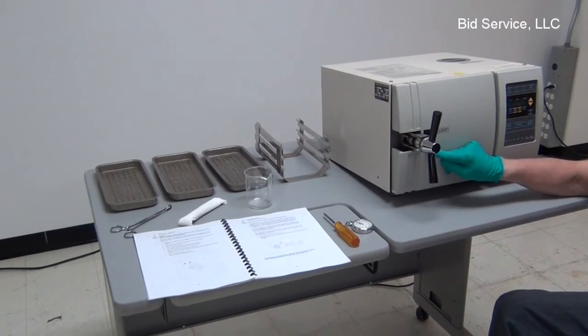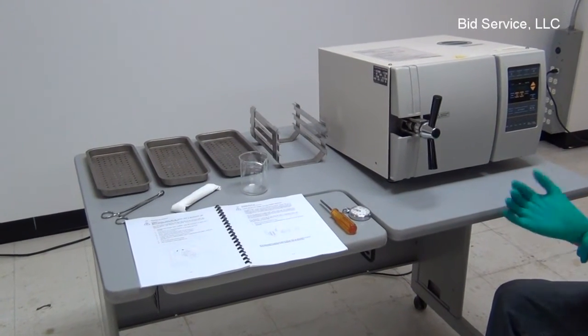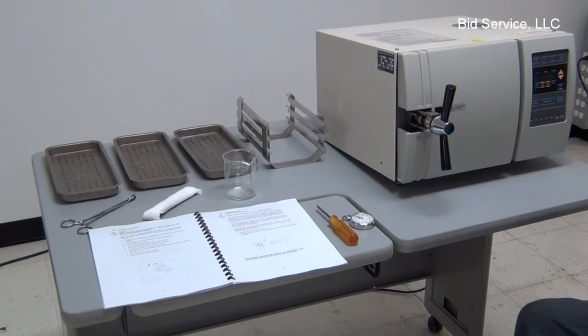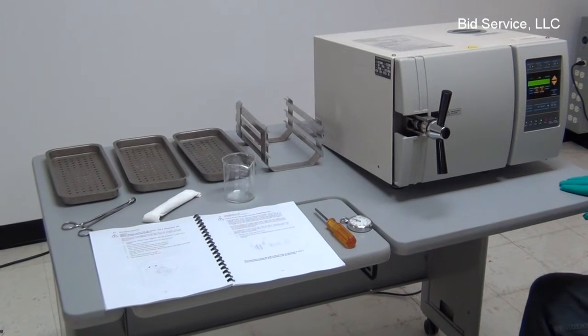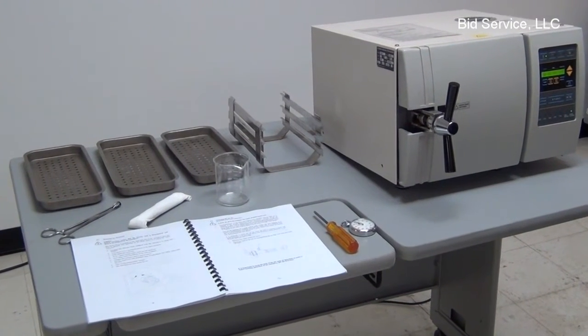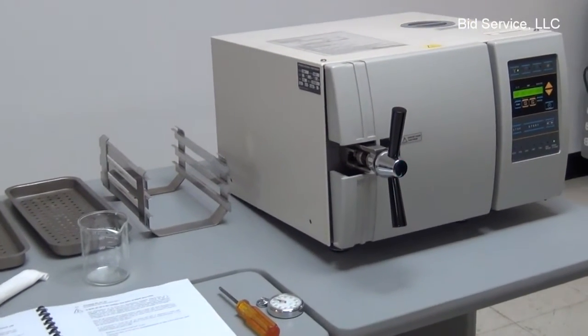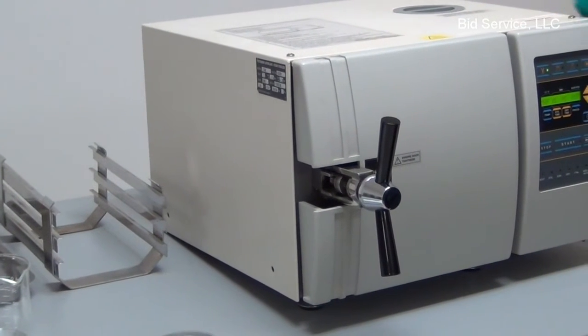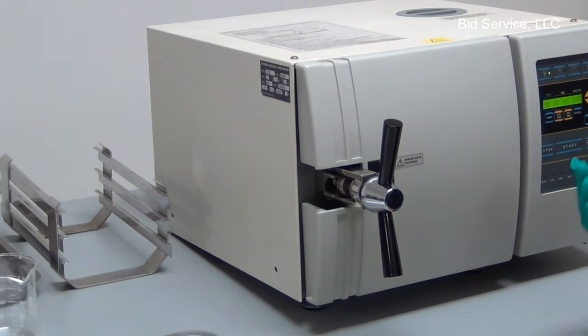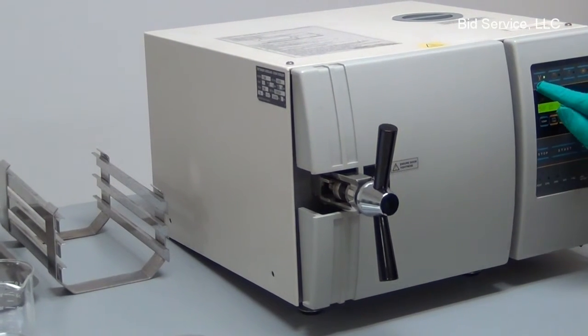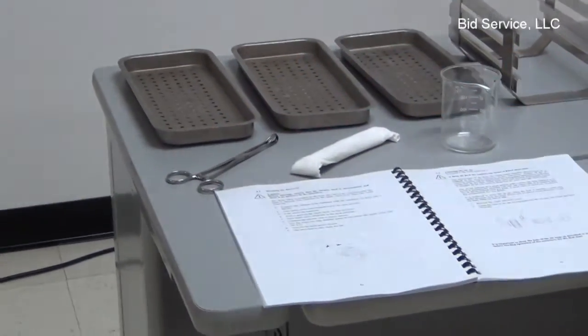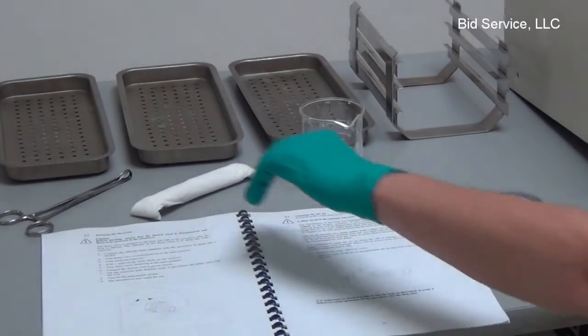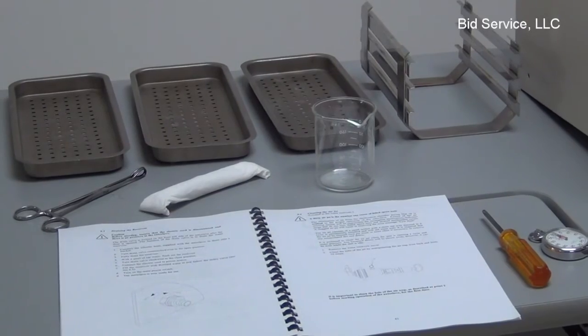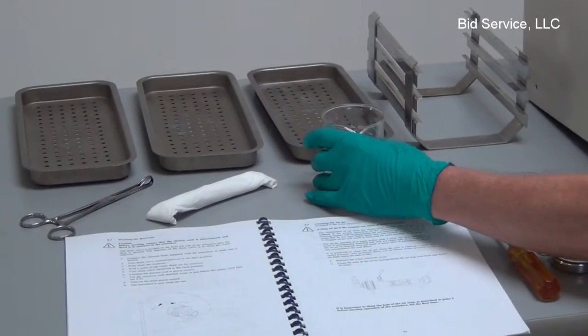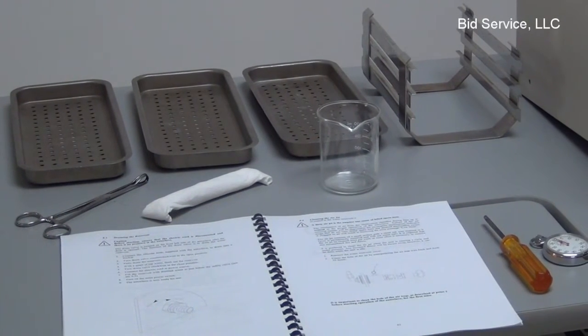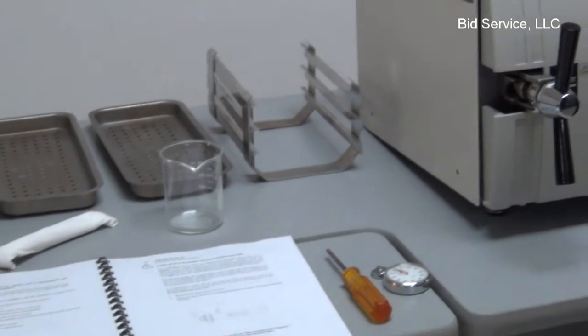This is the Tuttnauer 1780E automated autoclave. It's an excellent tabletop piece of equipment, very easy to use. Upon power up, it performs its own self-tests. It's very easy to program, and it has some pre-programming that is very common to the standards for using autoclaves. For example, unwrapped instruments for use. You can switch to wrapped instrument configuration, as well as glass vessels and other glassware used in laboratories. And of course, just drying if you need to simply dry something out.